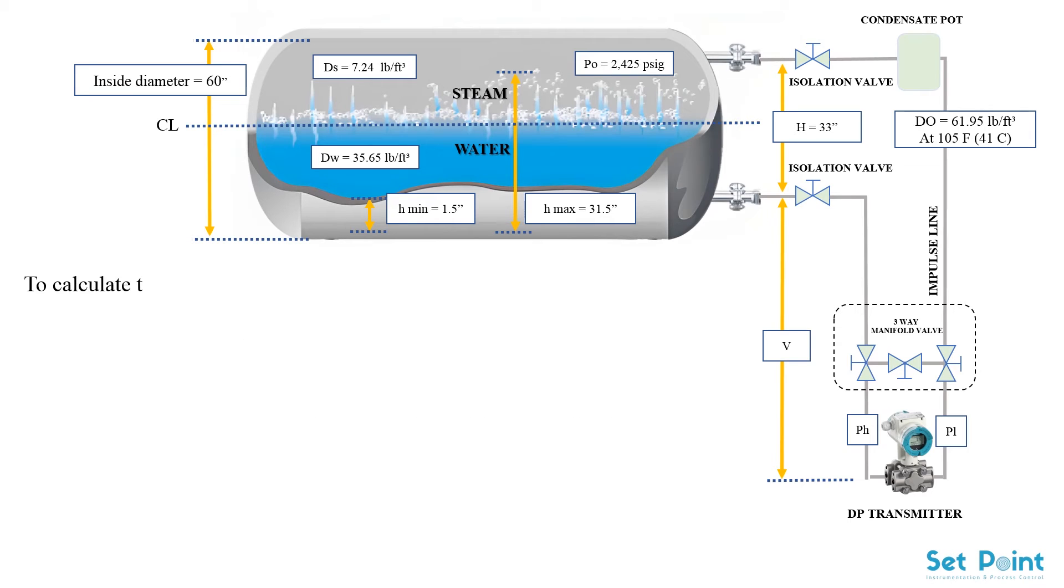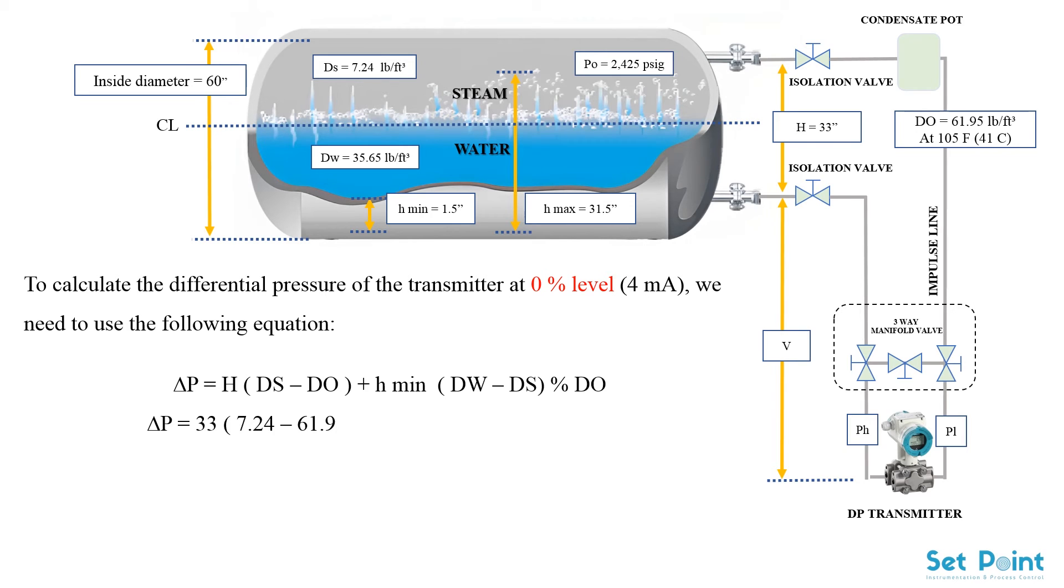To calculate the differential pressure of the transmitter at 0% level, the lower range value, we need to use the following equation. By entering the values, the result becomes as the following: lower range value at 4 milliamps equals minus 20.68 inches H2O.